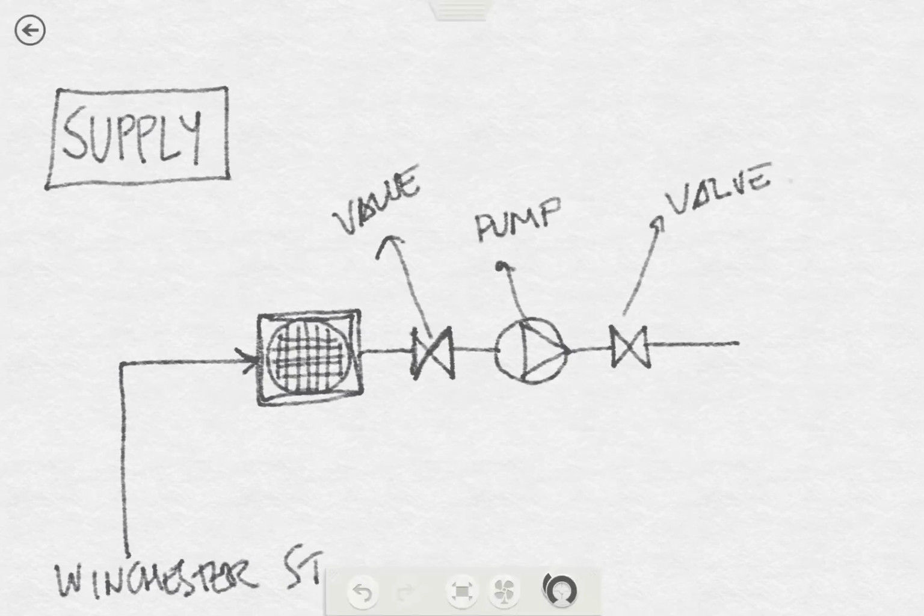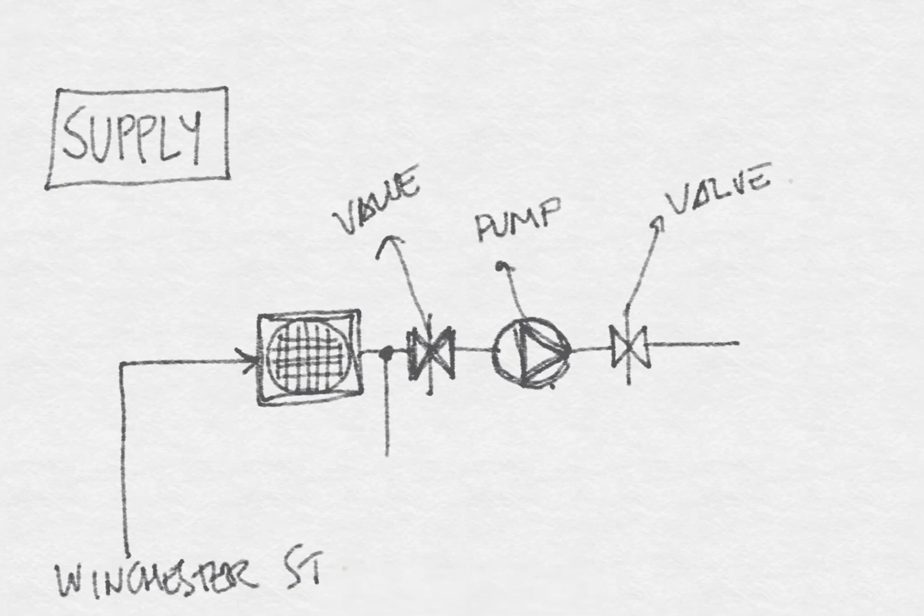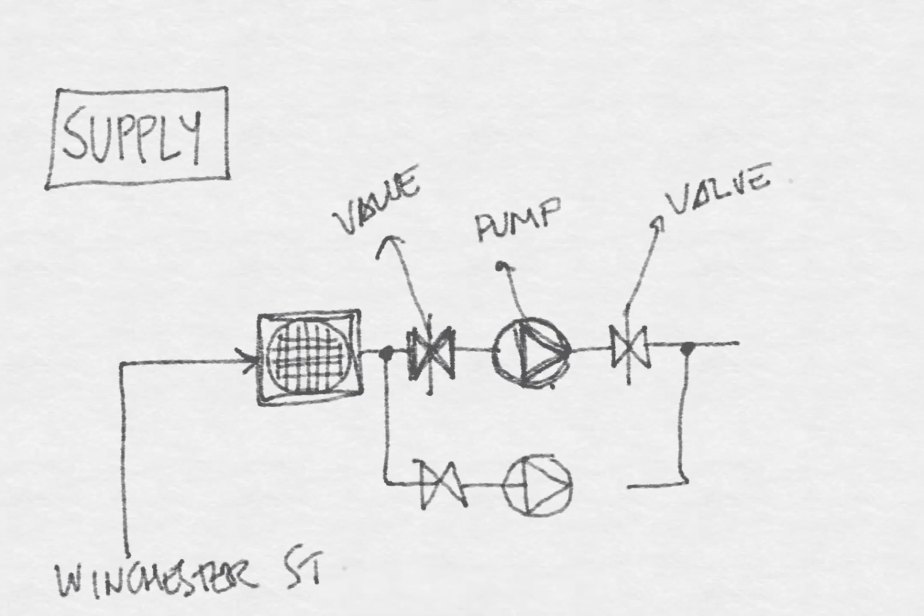When there's a water pump, and it's something important, if it's a water supply, we have these two valves because if there's a leak or a problem, we just cut off this circuit, and then we remove this water pump, and then we place another water pump, and then we open those valves again. Sometimes, if it's really important, we can have a bypass, and there is another water pump here.